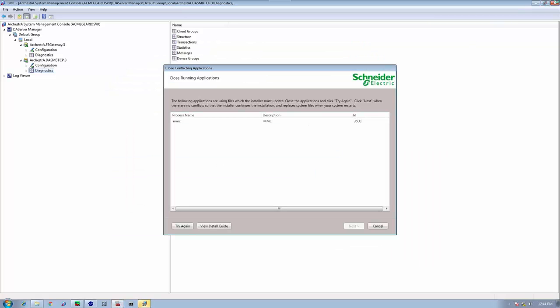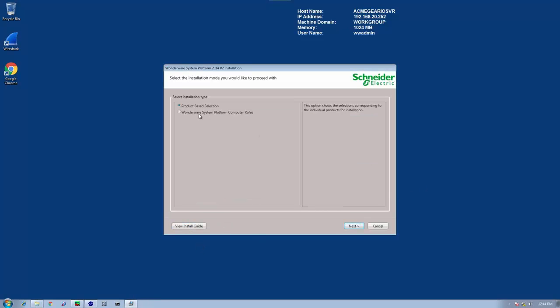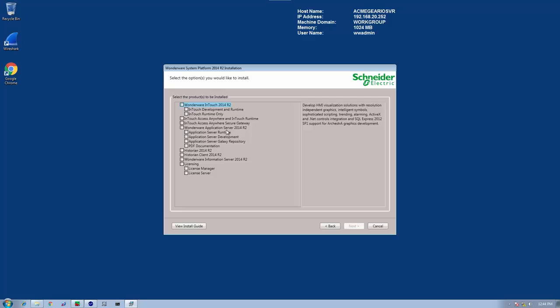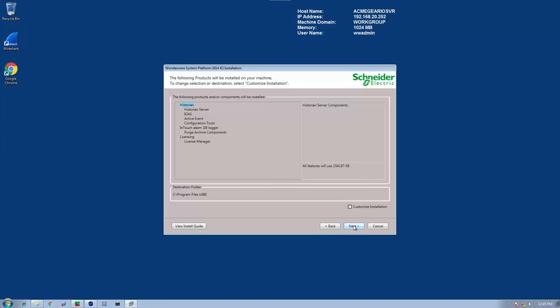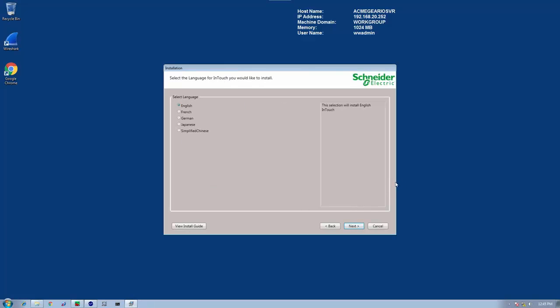Now let's shut down any Wonderware MMCs. Let's move on to the product base selection for the installation. Here it's important to select the correct component. Since the IDAS, or the remote IDAS in this case, is a part of the historian, we'll select it. We're going to select Customize Installation because we don't want the entire historian package. So we'll just simply unselect historian and select IDAS.